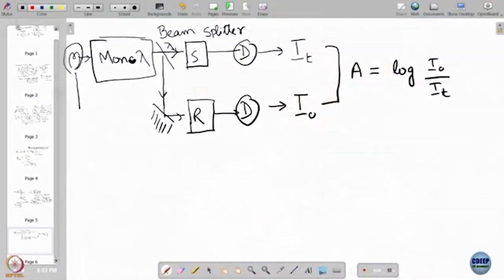Okay. That is one thing. The second thing is, what is the lamp here? Again, I will not go into detail because these lectures already exist in that spectroscopy course, but let me just say that for electronic spectroscopy in the UV visible range, you use a combination of lamps, deuterium lamp and tungsten lamp. Deuterium gives you ultraviolet, tungsten gives you visible.